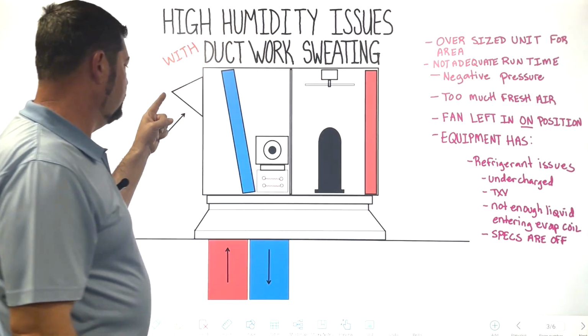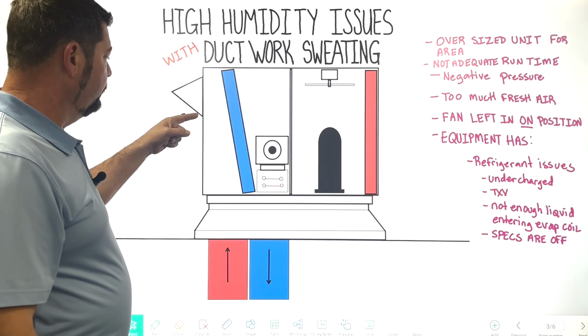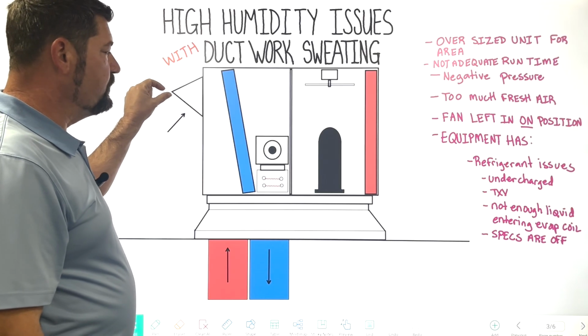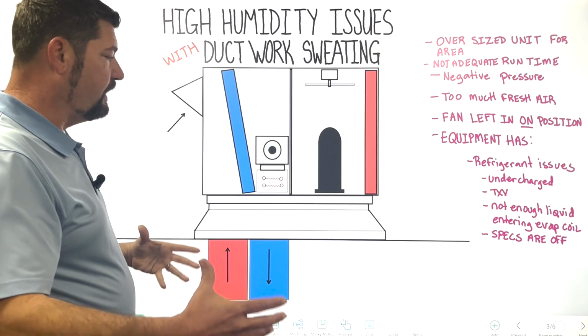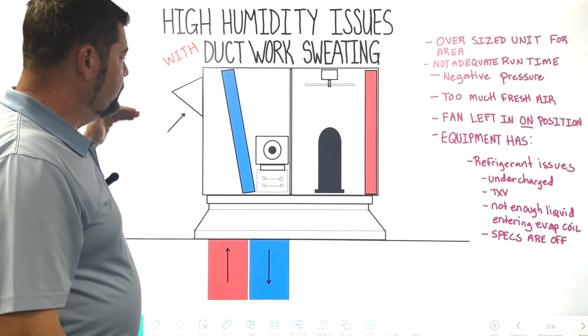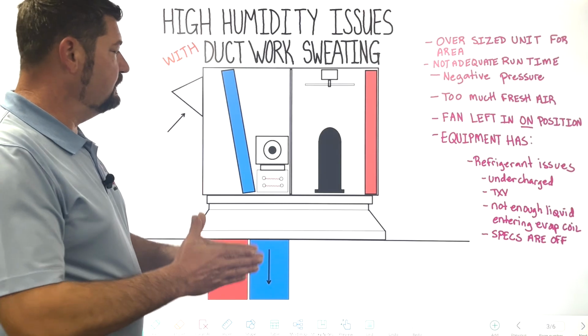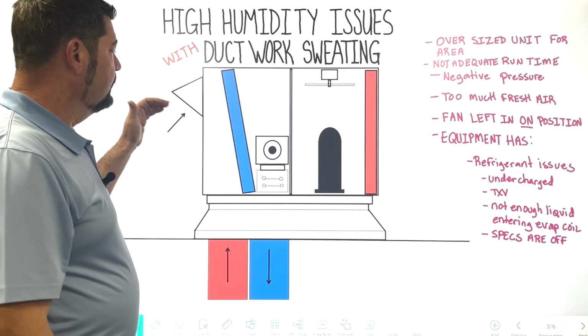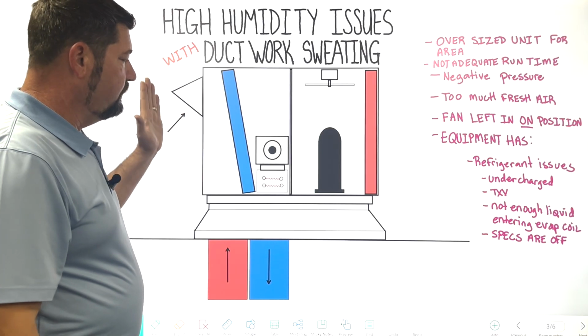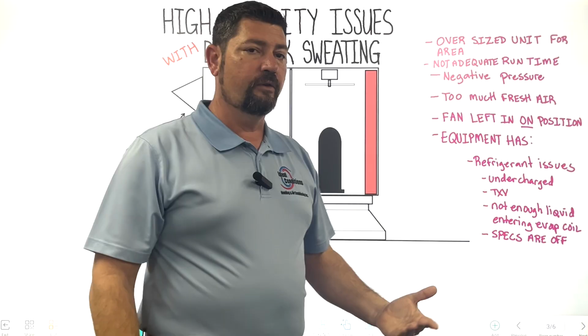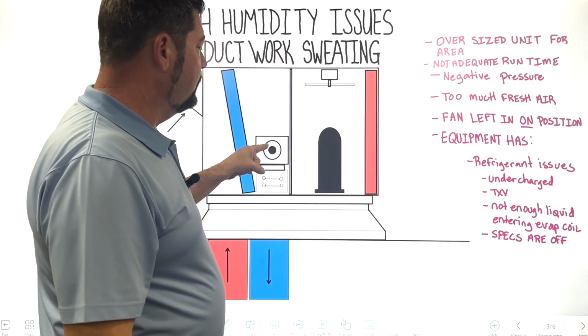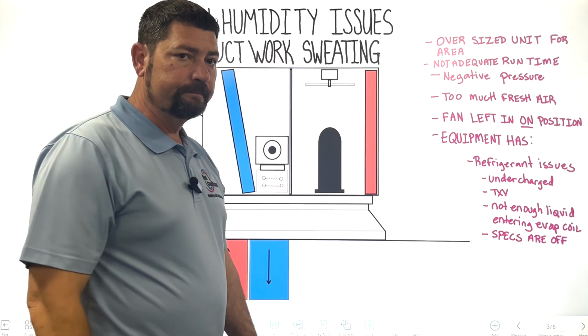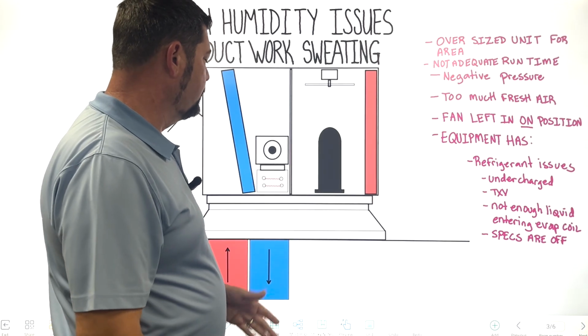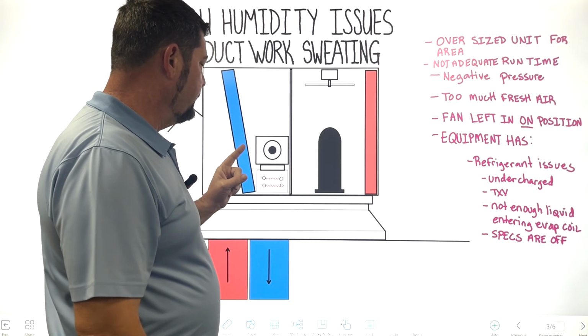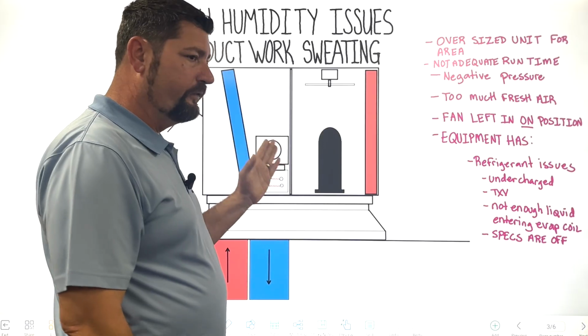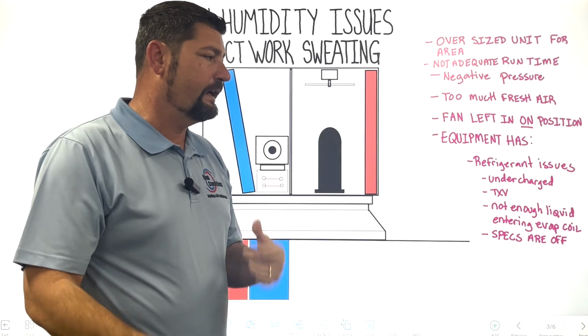So even if this mechanical damper is set to just barely be open, just enough to add enough fresh air to create a positive pressure, the humidity that's coming in by the fan being left in the on position is bad, because the thermostat should be in the auto mode, so the fan only comes on with a Y call. You don't want the fan to run unless it's calling for heat or it's calling for cool. You don't want the fan to run in the on position just to circulate air.